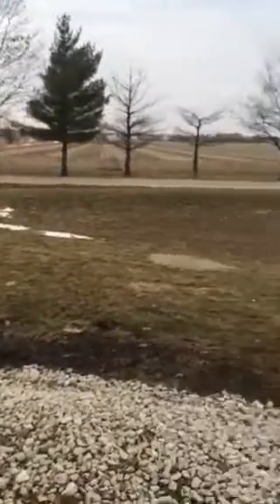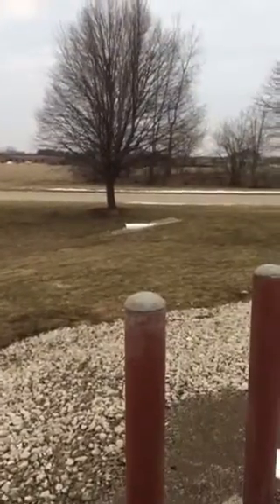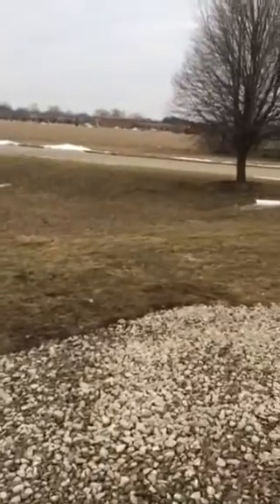Another thing that a lot of folks might want to keep in mind is that when propane leaks and it's not on fire, propane is heavier than air, so it's going to want to stick together and sink and find a low area. This fire station's been here about 20 years, and they built a low-lying retention area to help serve drainage. So in this particular case, if we do have a leak and it's not on fire, the propane is actually going to collect and pool down here.